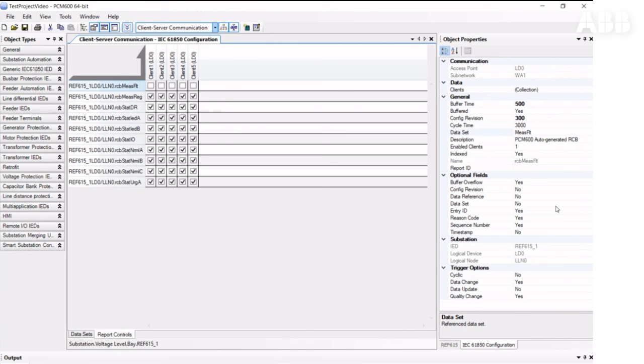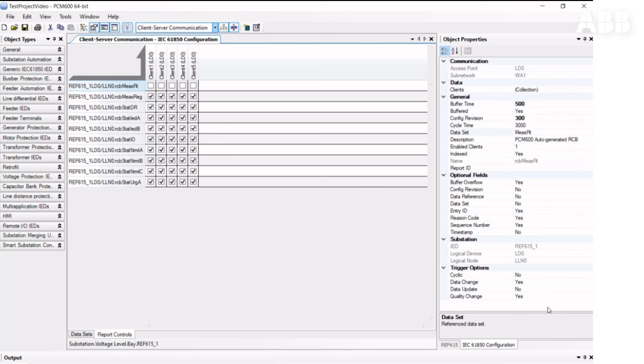In the Report Control tab, we can set up the Report Control block of our client server, and most of the settings are good by default. You may change triggering options if you have a specification to do it differently. Some SCADA systems require Report Control blocks to have a Report ID, and PCM600 does not automatically create a Report ID.